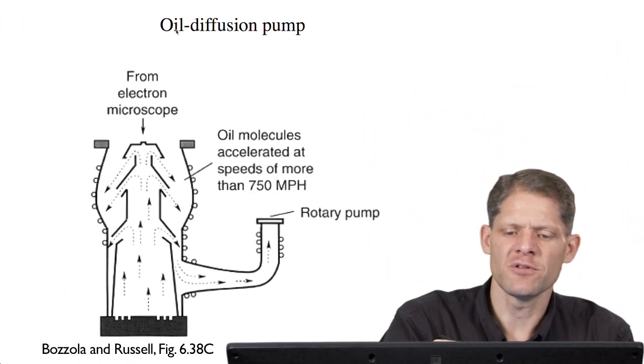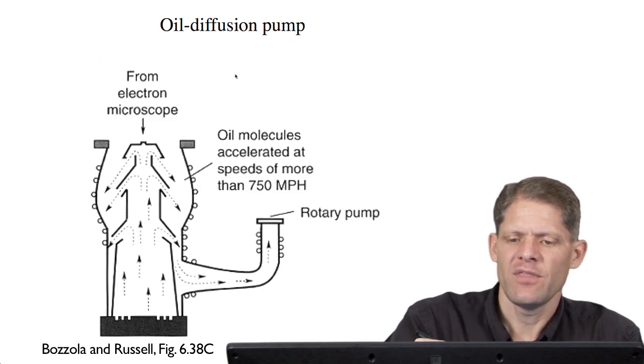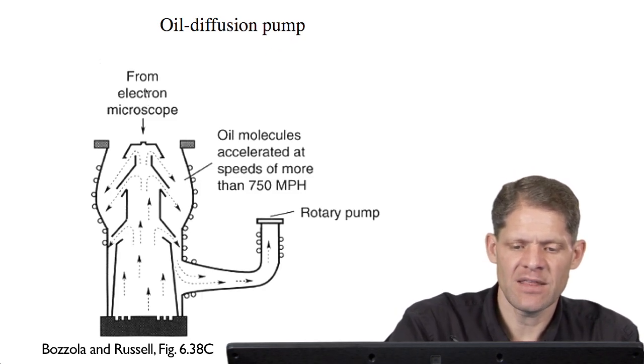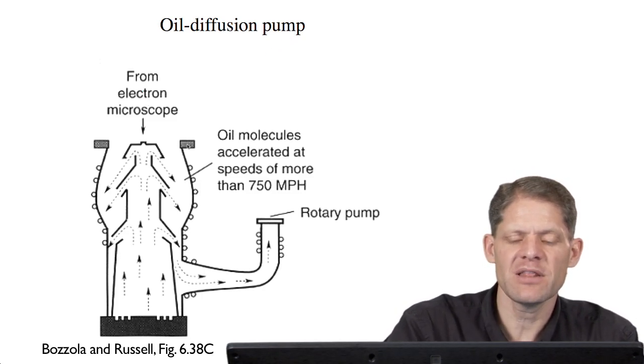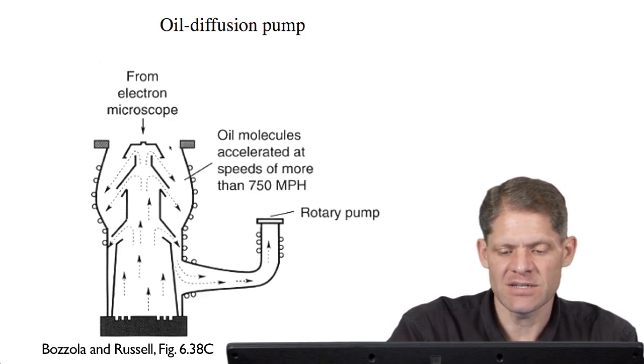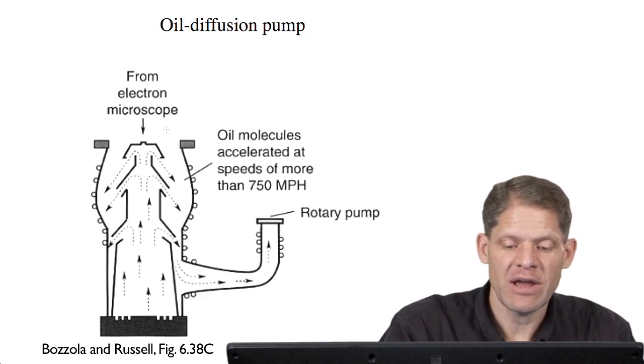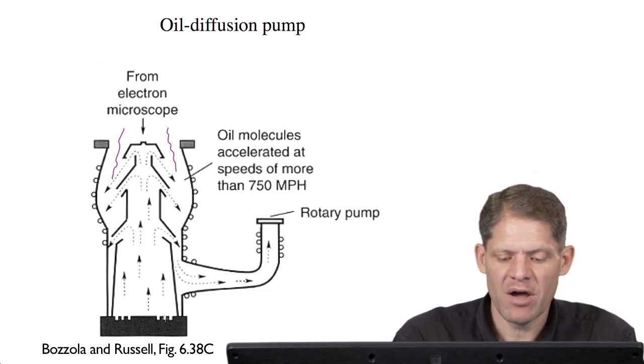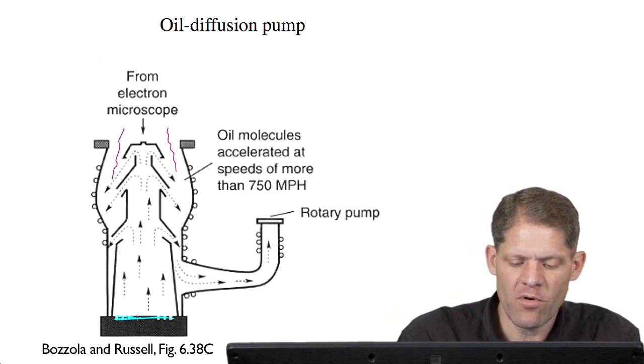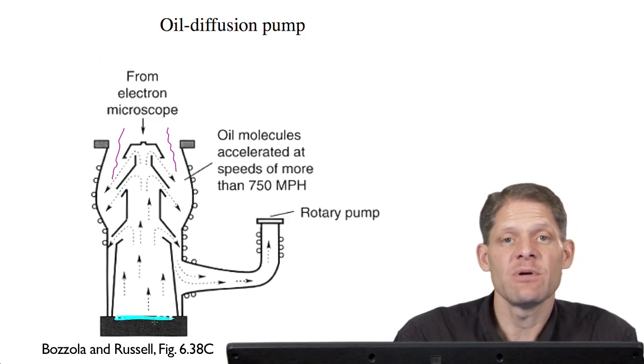which is the oil diffusion pump. The anatomy of this pump is that it's usually mounted directly below the electron microscope column. So the column connects into the top. Gases from the microscope column diffuse into these chambers. At the bottom of the pump, there's a reservoir of oil. And that reservoir is heated.